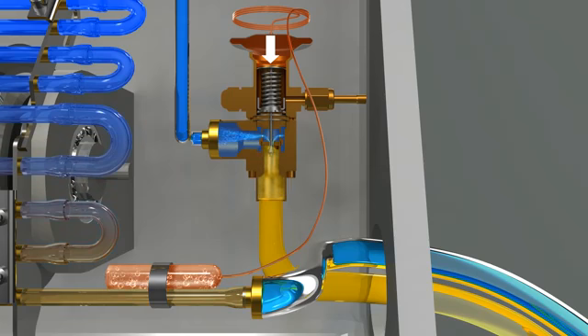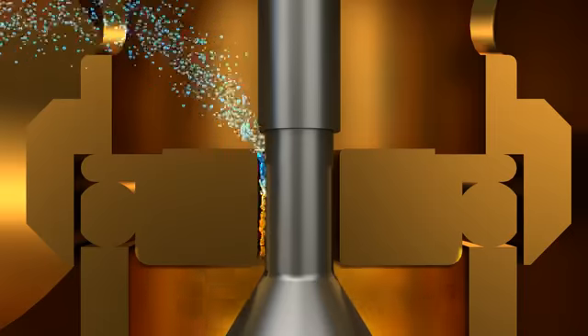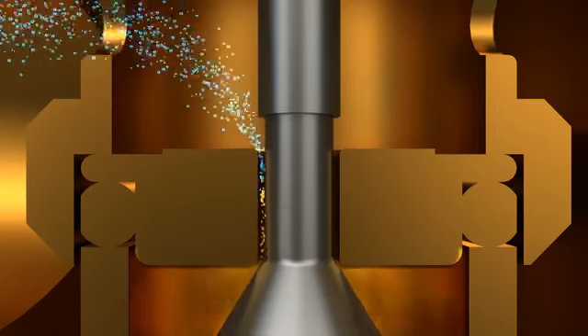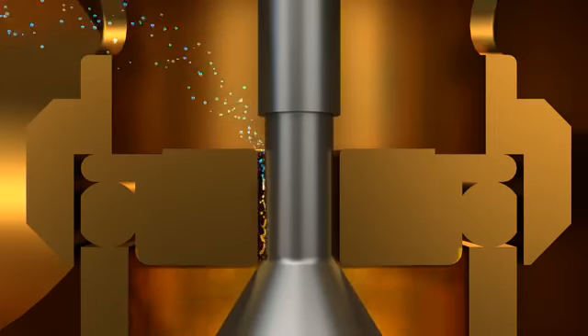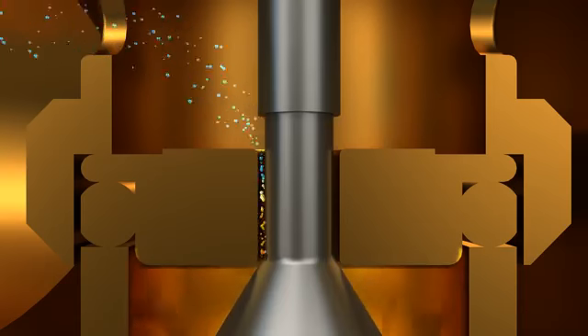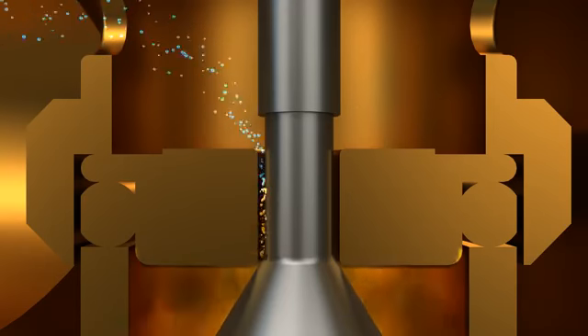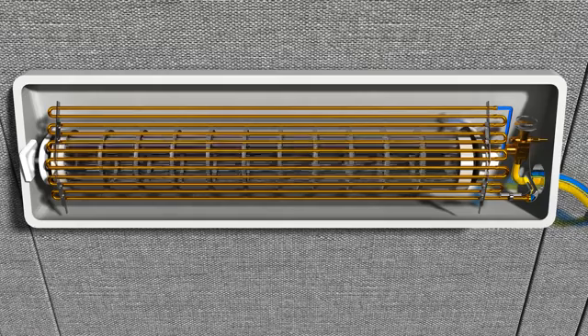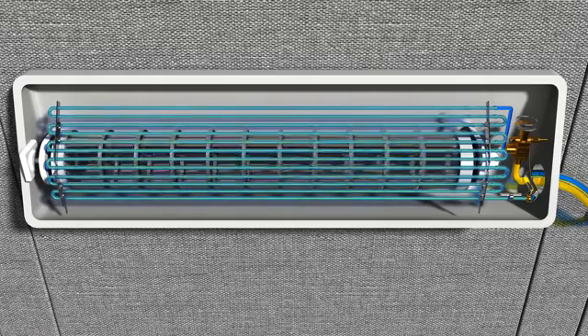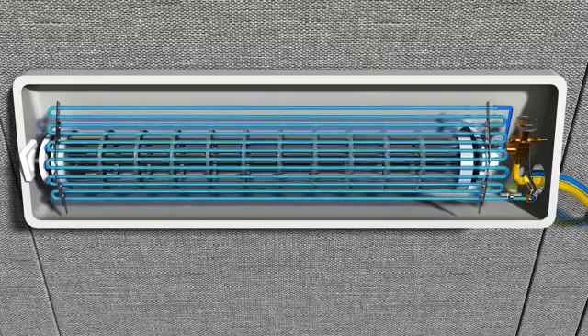When the temperature at the exit of an evaporator drops, gas pressure drops and the amount of refrigerant going into the evaporator in turn drops too. Applying the above principle, an air conditioner controls the amount of refrigerant injected into an evaporator to prevent overcooling. A refrigerant passes through the pipes of an evaporator and takes away heat in this process.